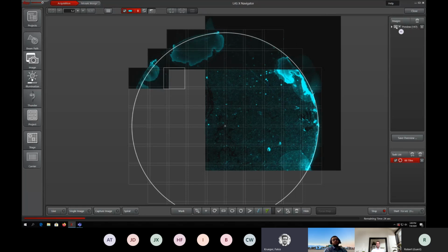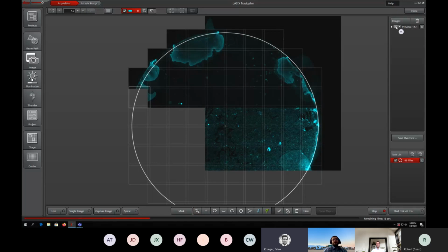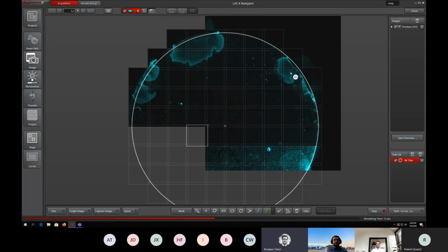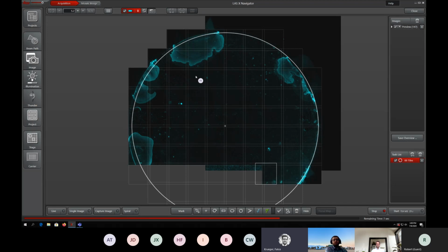Over this whole field of view you can see which areas are not interesting for my imaging and which areas are interesting for my imaging. For example, here you see some residual nail polish. This is problematic. Here the image quality will be bad anyway, so you leave those areas out by default.